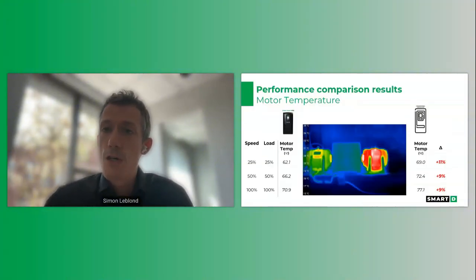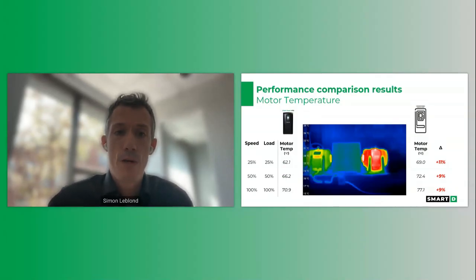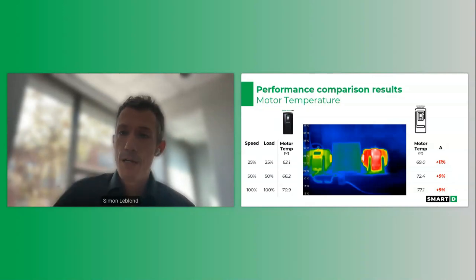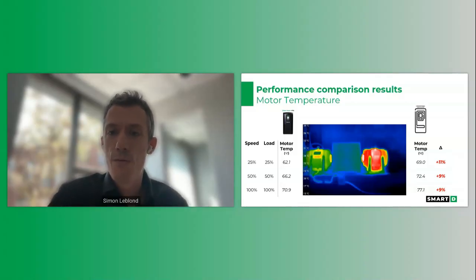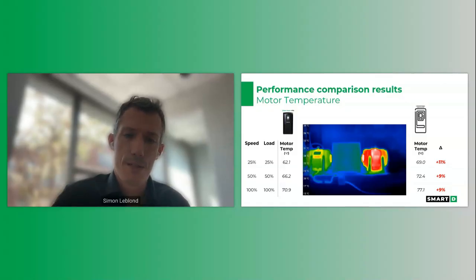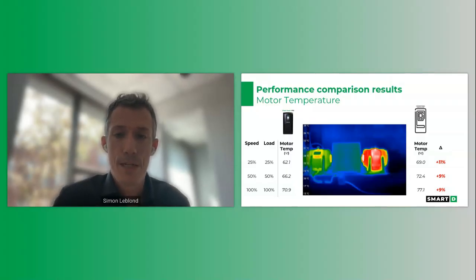Now, going back to the motor, you talked also about the impact of temperature on the motor lifetime. So here, it's interesting that because we're supplying the motor with a sine wave, at every speed and load combination you're seeing about a 10% impact on the motor temperature, where the motor temperature is much lower with the sine wave than with the square signal. And knowing, and I think you mentioned it, that every 10 degrees Celsius temperature rise has a 2x impact on the lifetime of the motor, really decreasing in half the motor life expectancy, this 10% difference, which is about 7 degrees Celsius, has a significant impact on the potential lifetime of the motor or your pump that you're running with your VFD.